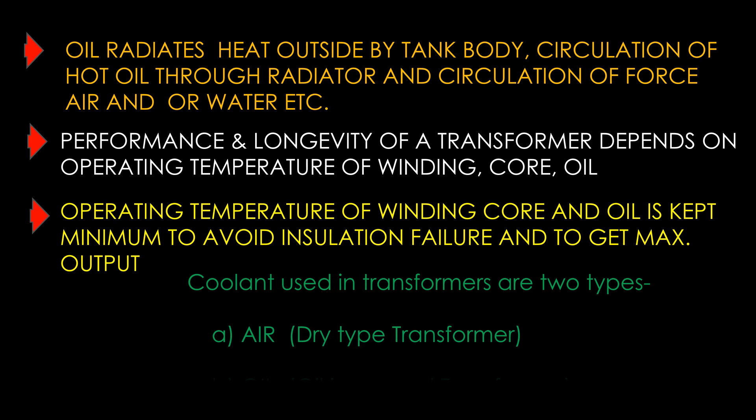Coolants used in transformers are of two types: A — air, and B — oil. Transformers using air as the coolant are called dry type transformers. In dry type transformers, generated heat is conducted across the core and windings and dissipated from the outer surface of windings to the surrounding air through convection. In the case of oil-immersed transformers, generated heat is taken and transferred by the oil to the walls of the tank through convection.